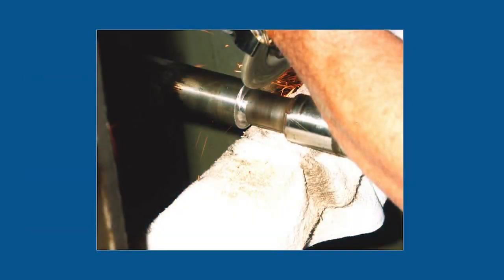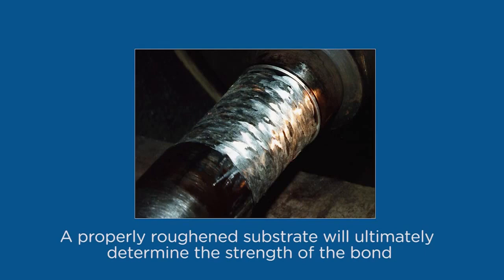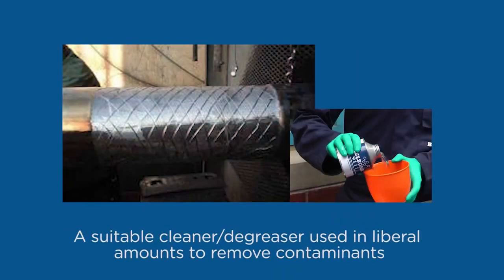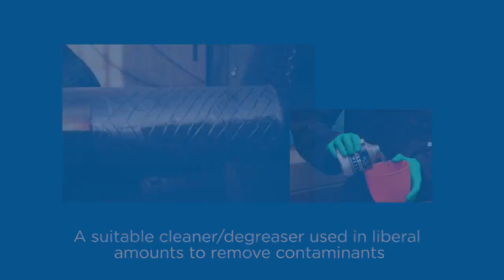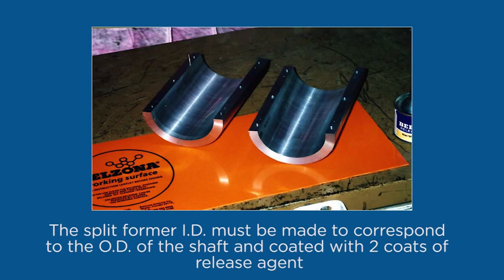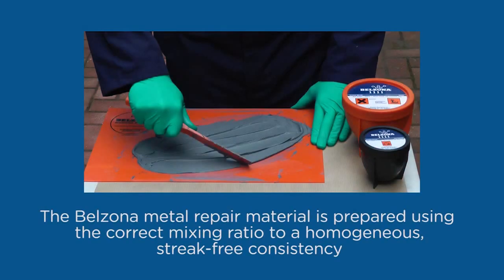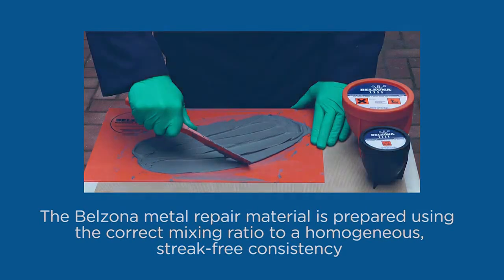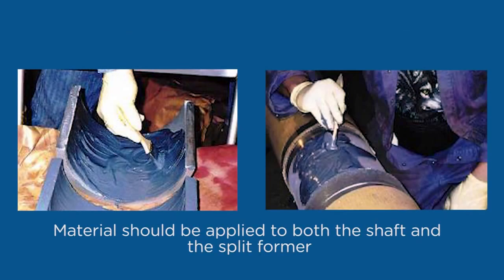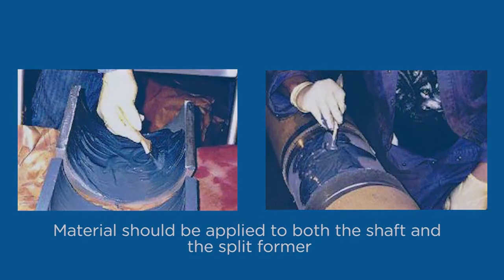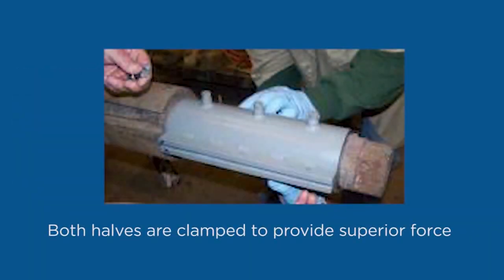First, they must be prepared to produce the appropriate surface profile to ensure an effective bond. A Belzona cleaner degreaser should then be used to remove surface contaminants. A forming device is then used with the inside diameter corresponding to the outside diameter of the shaft. After applying release agent to this former, the Belzona metallic polymer is mixed and applied in liberal amounts to the shaft as well as the former. Both halves are brought together and clamped, making sure the excess is squeezed out.